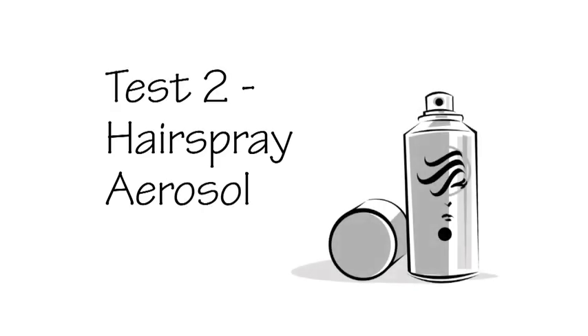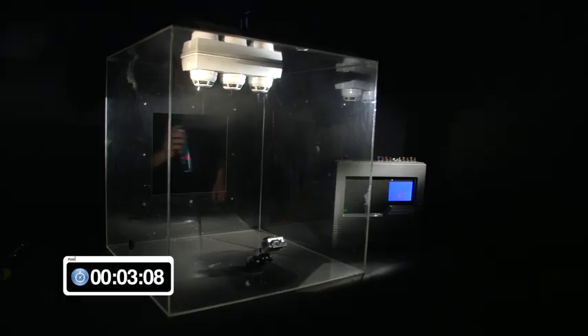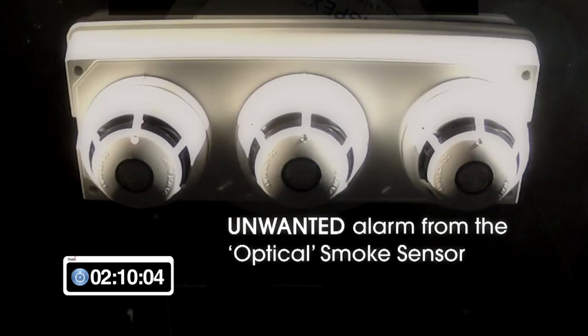Test 2: Hairspray aerosol. This test is to show the effect of a standard hairspray aerosol being sprayed on the three different types of detectors. A typical amount of hairspray is sprayed directly across the three detectors. After approximately 30 seconds, the optical smoke detector produces an alarm condition as the optics of this device have sensed a similar phenomenon as would be produced by smoke. The test was allowed to run for approximately 2 minutes, and during this time the heat and CO detectors did not produce any alarm conditions.